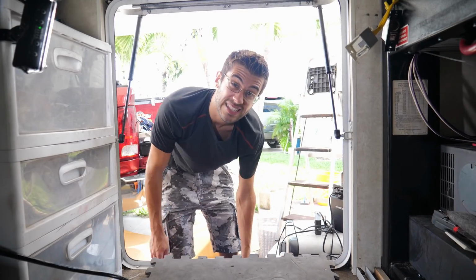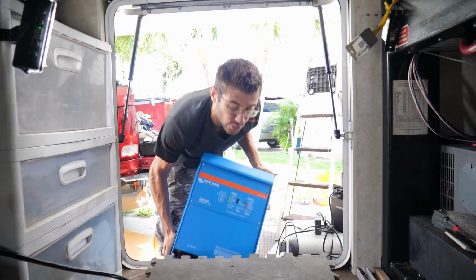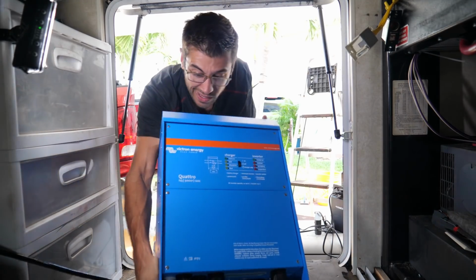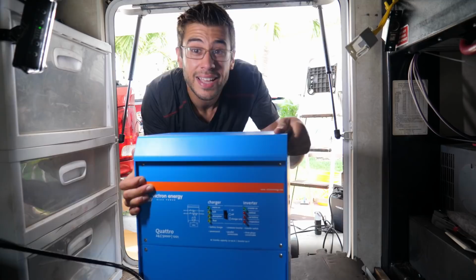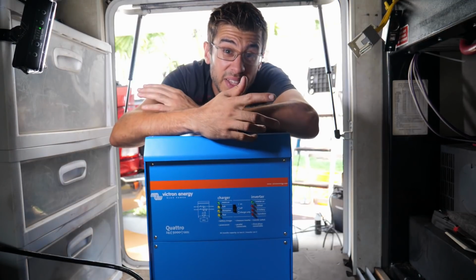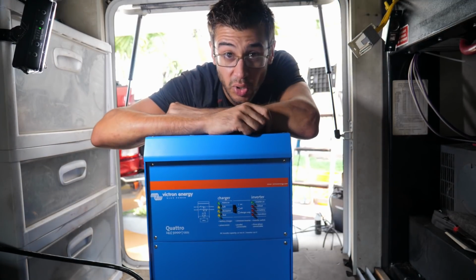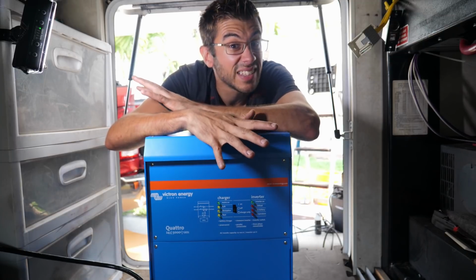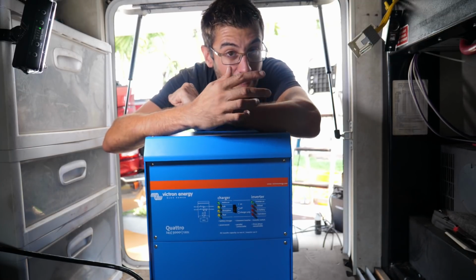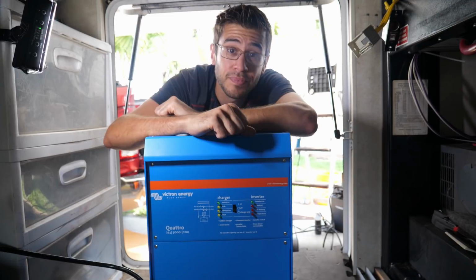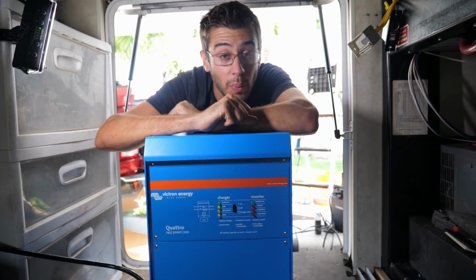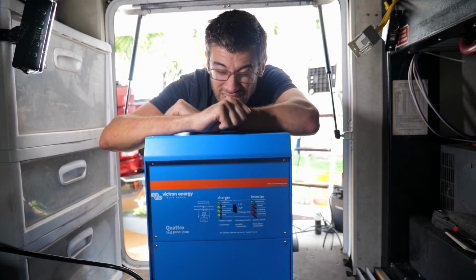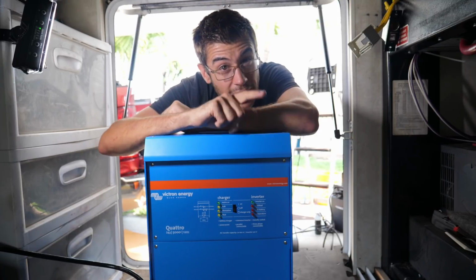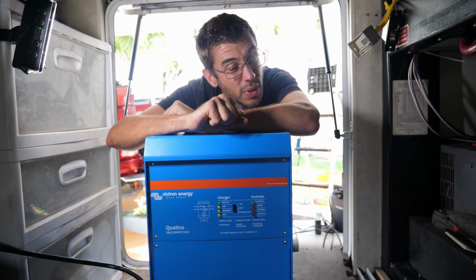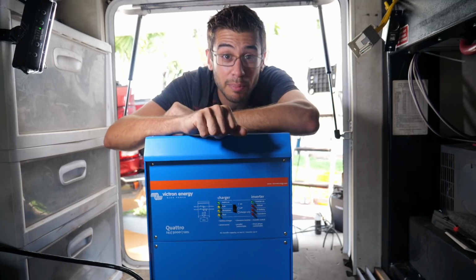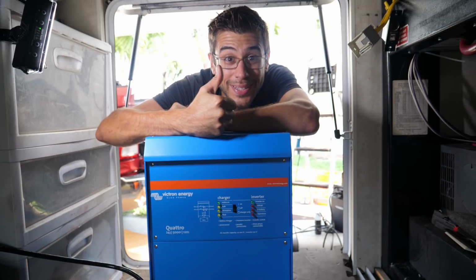Now that we've got the batteries and the bus bars installed, the next order of business is installing the inverter. Now this is the biggest, heaviest piece of electrical equipment we're installing. It's basically a generator between the batteries and the AC system. This 5,000 volt amp unit weighs 66 pounds, so it's a little tricky to move around, but we already test fit it. We know where it's going to go. We just need to build the brackets, secure it in place, and hook it up.